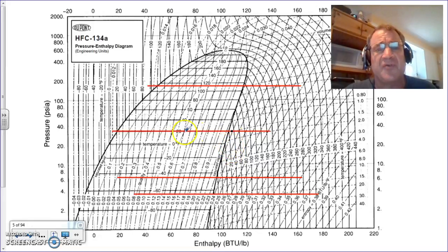And then by the time we get to the inlet of the compressor, we're probably running at a temperature of about 45 degrees Fahrenheit right here, because typically we have around 25 degrees of compressor superheat by the time the suction vapor travels down the suction line. A couple other typical temperatures: if we're at 115 degrees condensing, we're looking for roughly 10 degrees of subcooling.